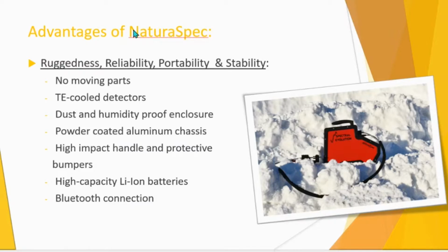For portability, the NaturaSpec has a handle, a high impact plastic handle on top, which makes it very easy to move not only from side to side, but if you're using it in the lab, you could move it from one table to another table or from one room to another room. Our instruments come as well in a custom-made backpack, so they are very portable in the field. They come with high-capacity lithium-ion batteries. Those custom-made batteries last for quite a long time. Under typical field conditions, taking measurements nonstop, your battery will last about 5 to 6 hours. So with 2 batteries, you can cover more than 1 day of data gathering in the field.